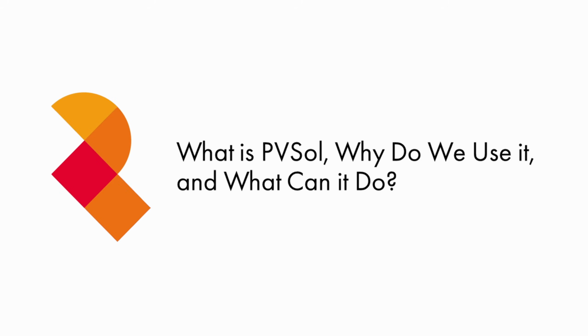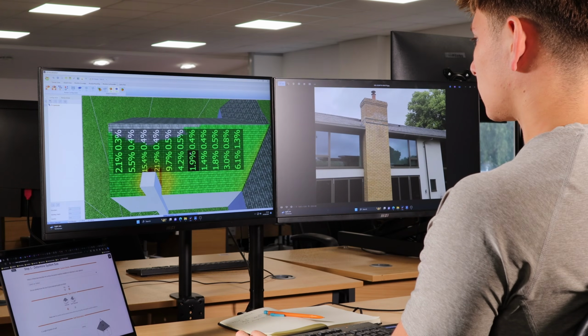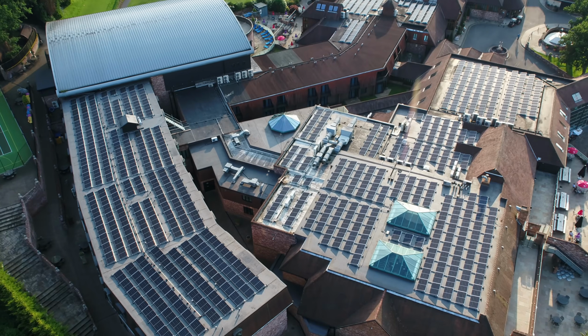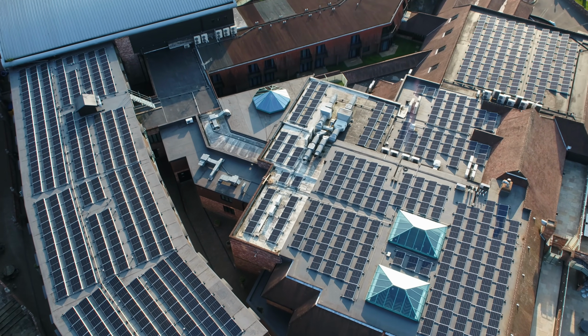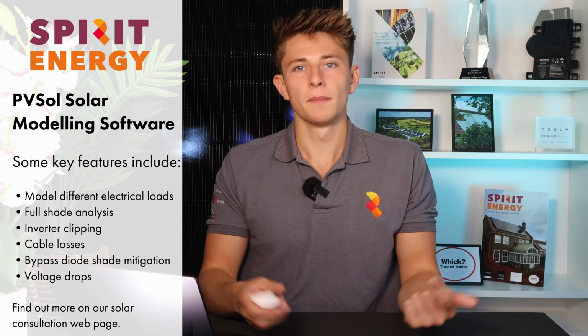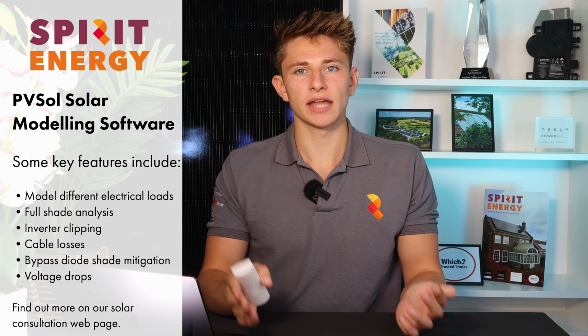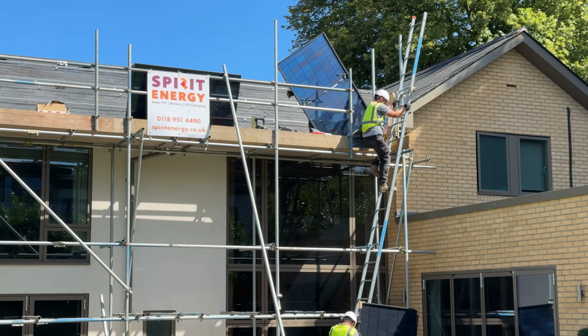Every good solar installer should have an advanced piece of software that allows for complex modelling, like PV-Sol. We use it for a lot of our residential and commercial projects, and it comes with a wide range of benefits. You can run a full shade analysis, as well as very detailed performance models. Using PV-Sol, you can accurately model for any major electrical loads at the property, such as electric vehicles, heat pumps and swimming pools. You can also model things like inverter clipping, cable losses, bypass diode shade mitigation, voltage drops, and even the generation increase from reflection on the back of any bifacial panels.